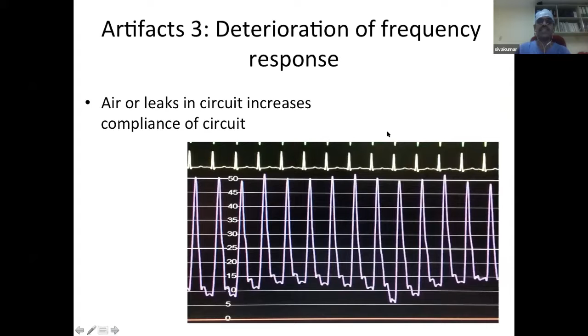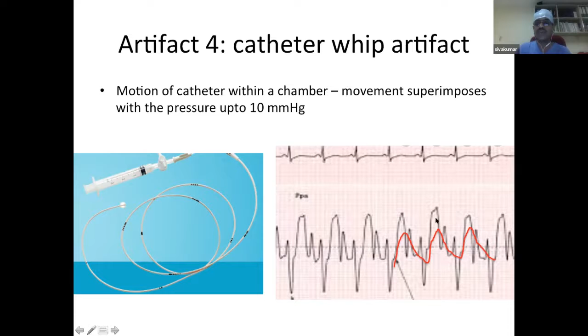The next one is called catheter whip artifact. It is the motion of the catheter within a cardiac chamber. A typical example is pulmonary artery pressure recorded with a Swan-Ganz catheter, which keeps popping up and down. So you get a trace where the systolic and diastolic show many extra traces. Ideally it should be smooth, but there is too much catheter whip, and each time the balloon floats toward or away, it produces too much artifact. This is called catheter whip artifact.